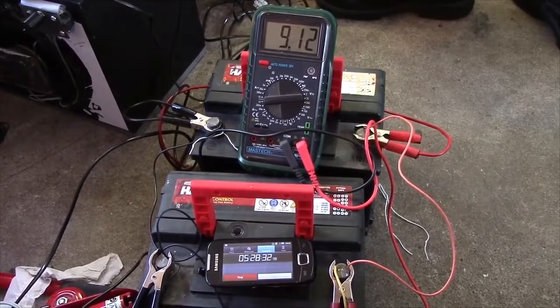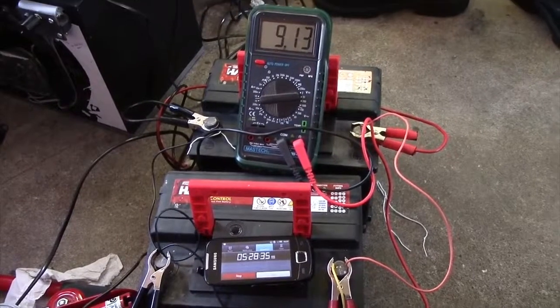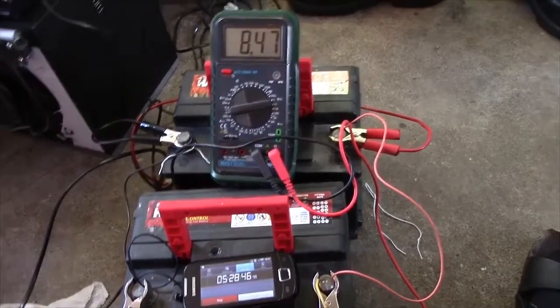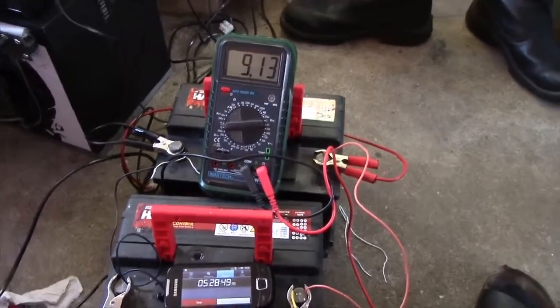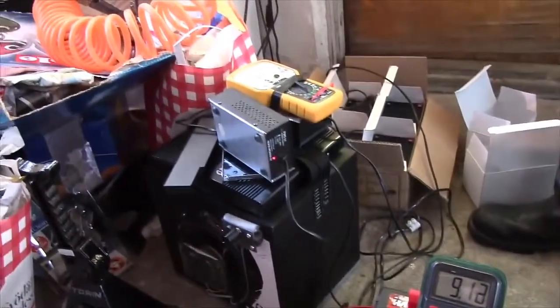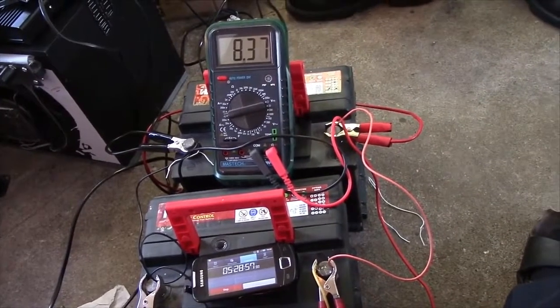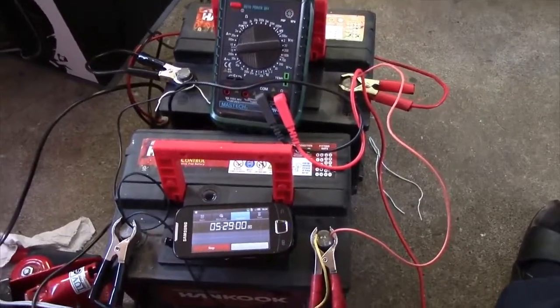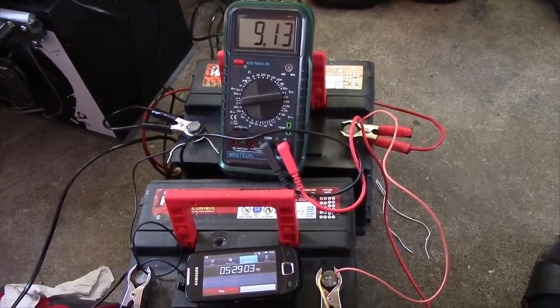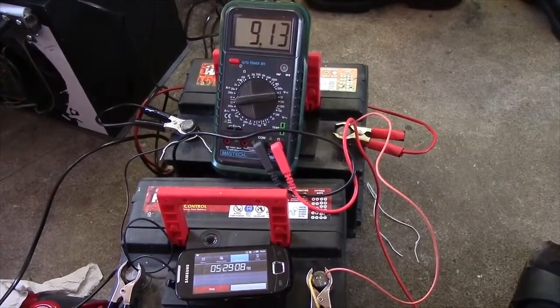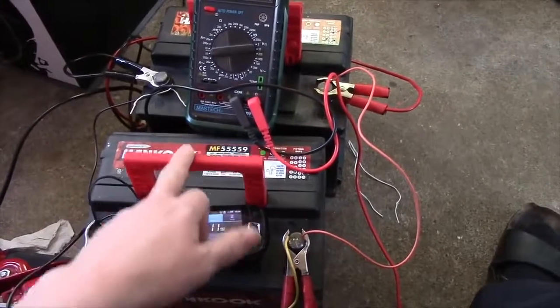And there we go about 5 hours in. Well 5.5 and we're down to about 9 volts still with the load connected so they aren't entirely empty yet. But I'd say these batteries could deal with them charging now. So I'm just going to hook up my normal 7 amp charger and let them slowly charge back up. Doing them off we've drawn about 50 amp hours out of them, which since it's over such a short amount of time that's actually a fairly good value. Because batteries are usually specified over a 20 hour period, so they're less than 20 hours of discharge time and they can have less capacity. So with a bit of luck these can still be saved.